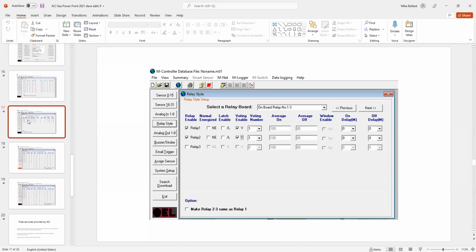And then our next step is to set up the relays on here. So we're going to use 2 relays. Relay 1 is going to be for our low alarm. Relay 2 is going to be for our high alarm. We're going to set it up as non-latching and voting, which simply means that if any of those sensors detect a level, it's going to turn the relay on.